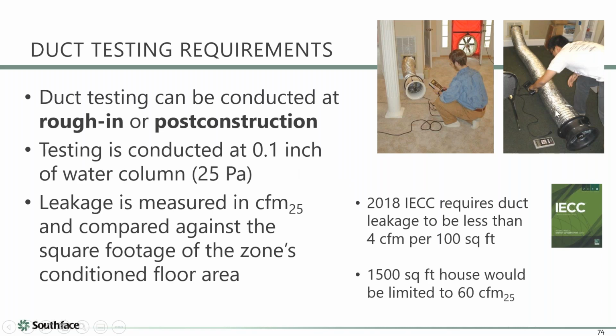This is an accurate fan, and it can measure the amount of CFM. The amount of CFM it takes to pump up the ducts to 25 is equal to the amount of CFM that's leaving through the leaks. So the code says you can have 4 CFM of duct leakage for every 100 square feet of conditioned floor area. So we would say 4% of the floor area is the allowed amount of duct leakage. If it's a 1,500 square foot house, you'd have to come in tighter than or equal to 60 CFM, and that little subscript 25 is telling us that we're testing it at 25 pascals.